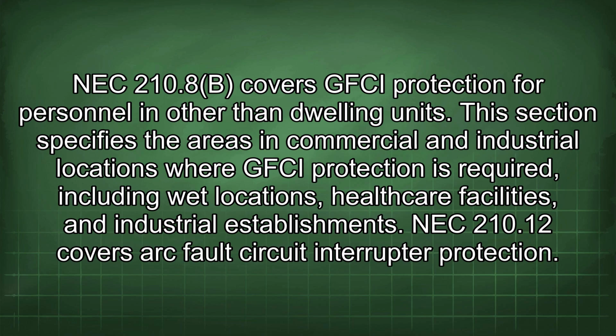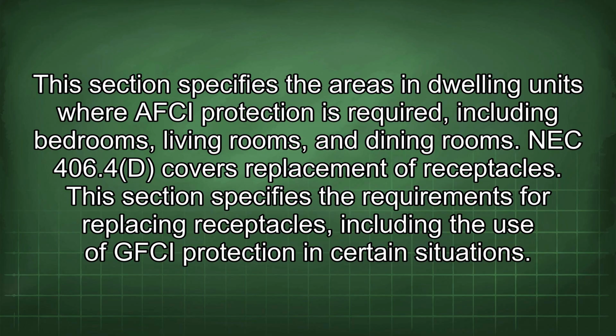and industrial establishments. NEC 210.12 covers arc fault circuit interrupter protection. This section specifies the areas in dwelling units where arc fault protection is required, including bedrooms, living rooms, and dining rooms. NEC 406.4(D) covers replacement of receptacles. This section specifies the requirements for replacing receptacles, including the use of GFCI protection in certain situations.